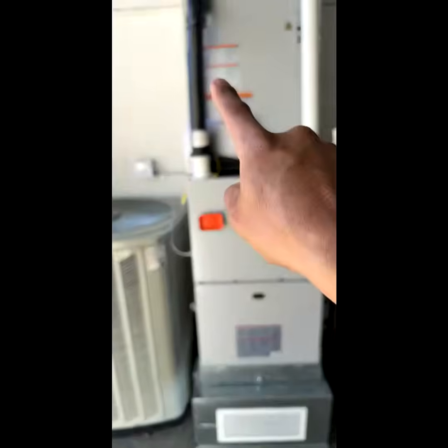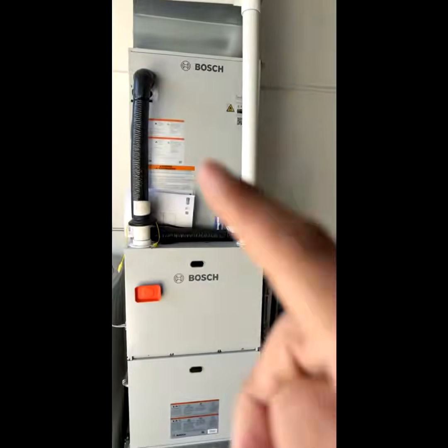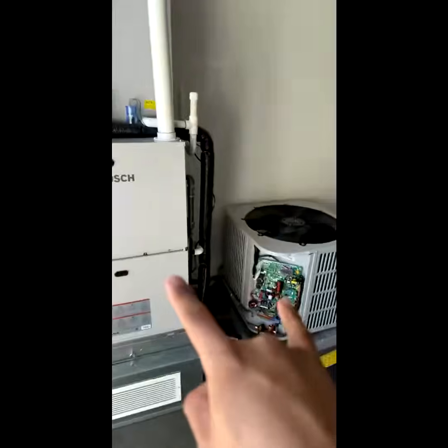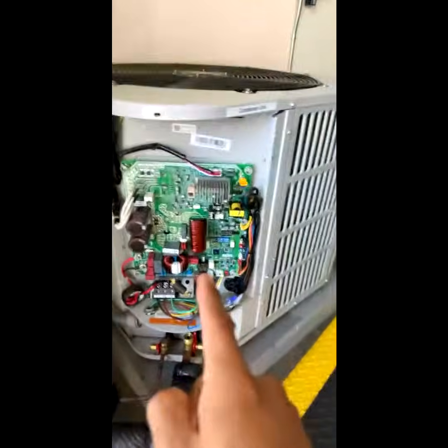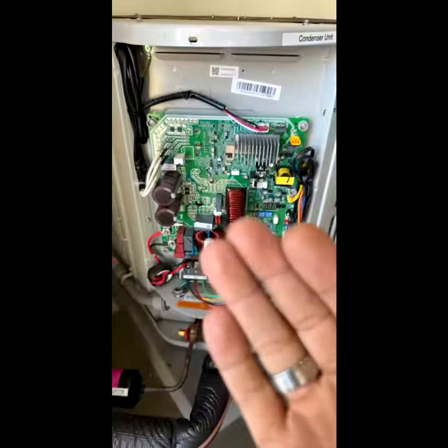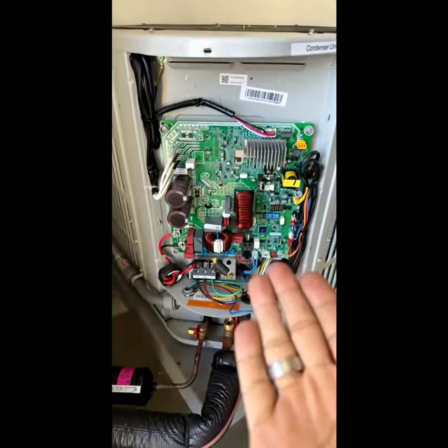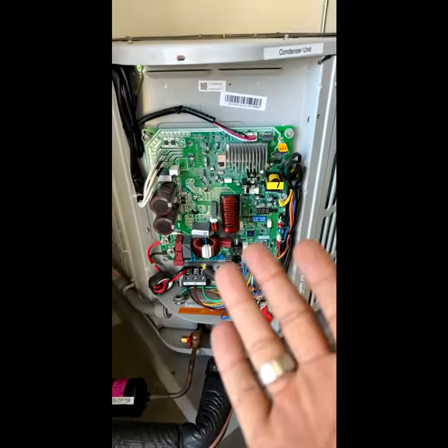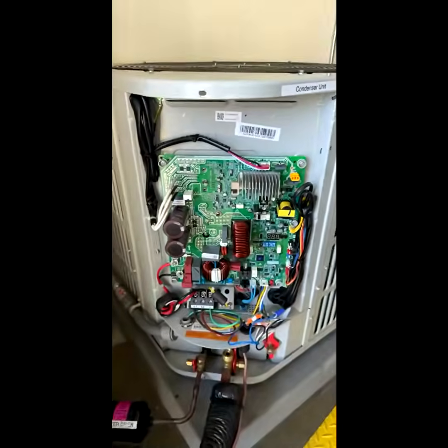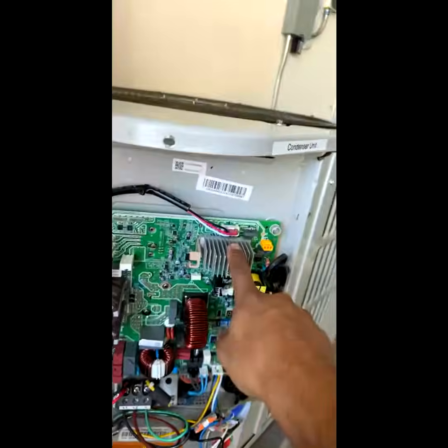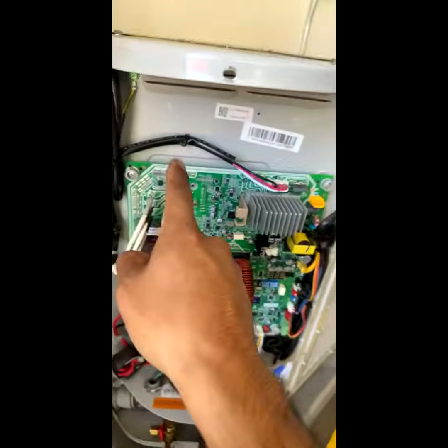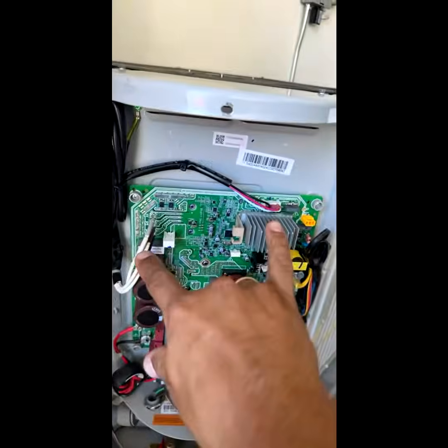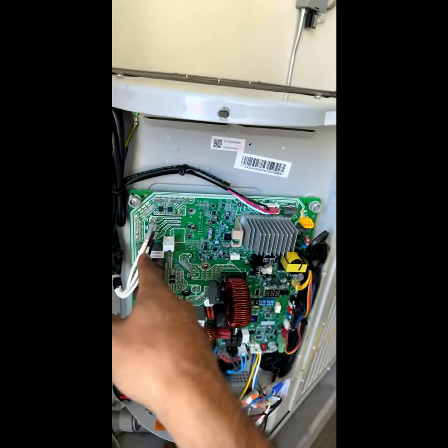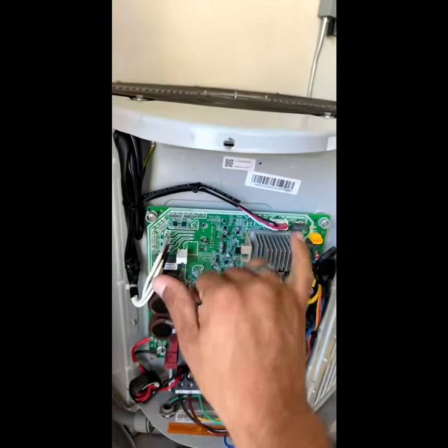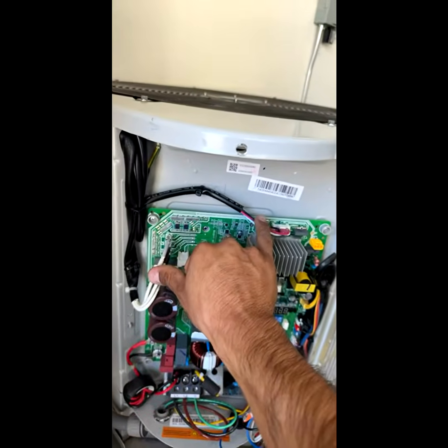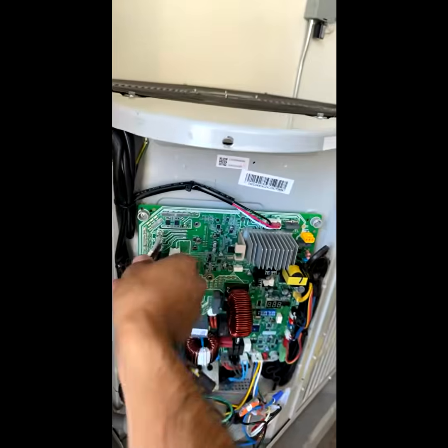You have an A2L sensor, this is a 454B refrigerant. These inverters, these boards, I get why they're trying to do this, these are awesome because you save a lot of energy, but look at all this craziness. You've got your heat sink here, your condenser fan and your compressor. It uses a rotary compressor, and it's DC, but you can read it in AC voltage for your condenser fan and compressor.